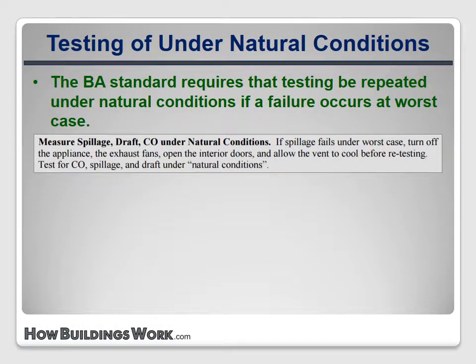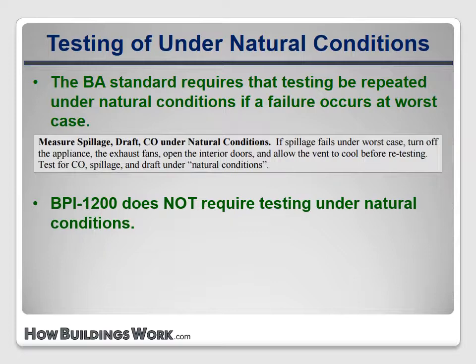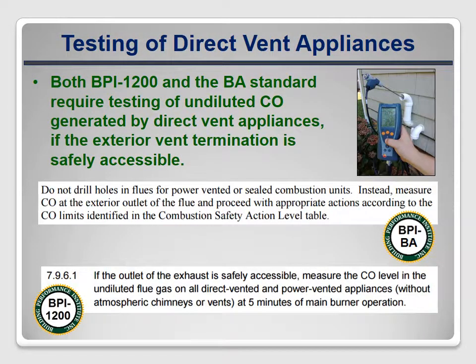The BA Standard includes a requirement that any appliance that fails the spillage or CO test under worst-case conditions be retested under natural conditions to help diagnose the reason for the failure. BPI 1200 does not include this requirement. Both standards require testing undiluted CO levels on direct vent appliances by measuring at the exterior termination. BPI 1200 adds the phrase 'if the outlet of the exhaust is safely accessible,' so you don't have to climb on the roof to get a measurement.